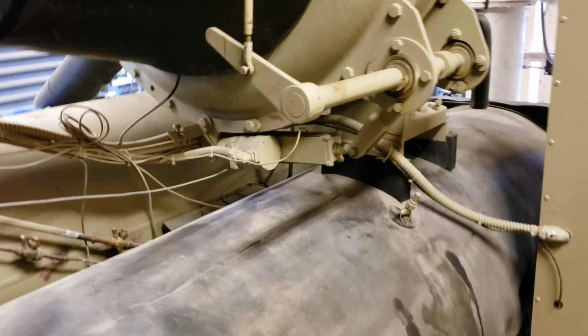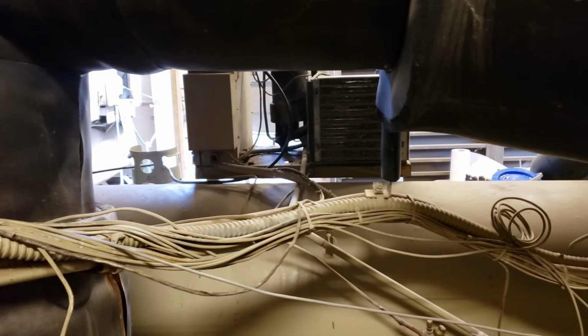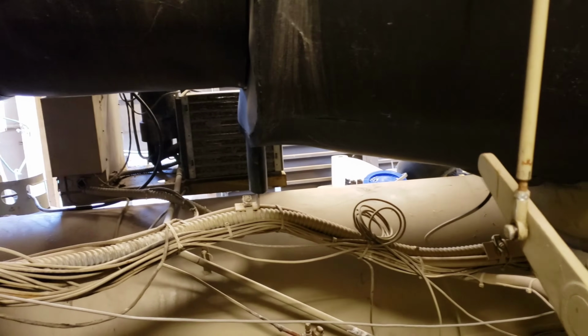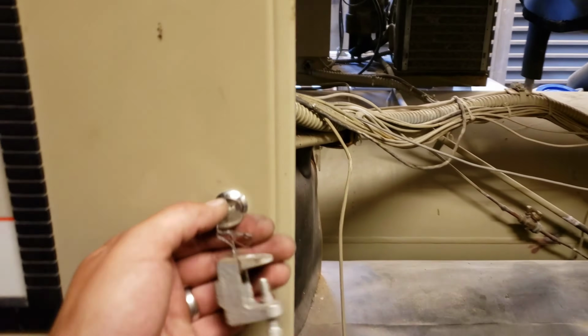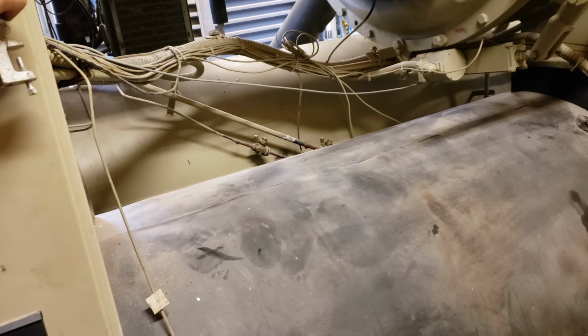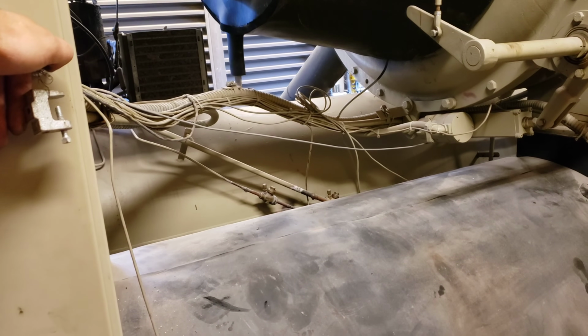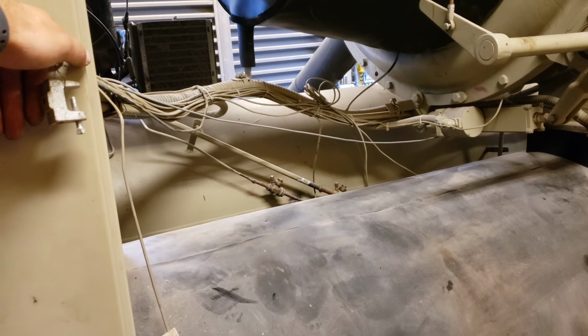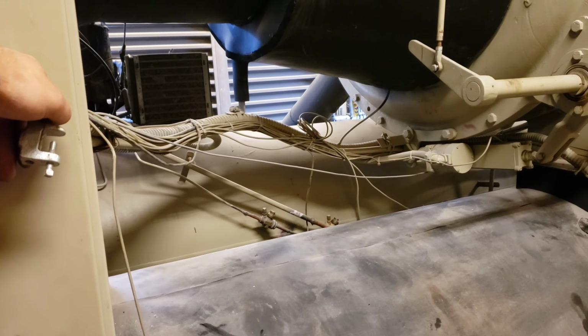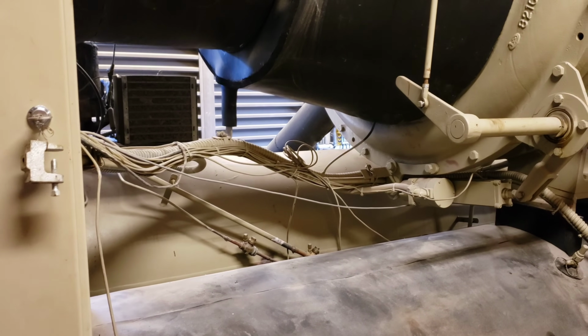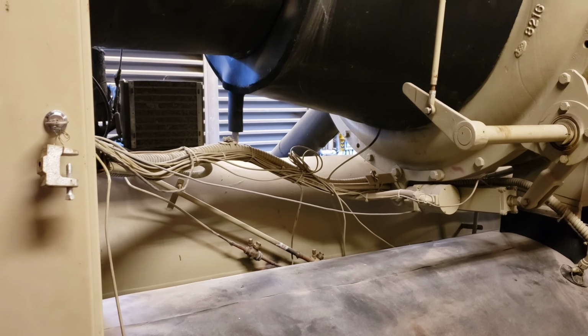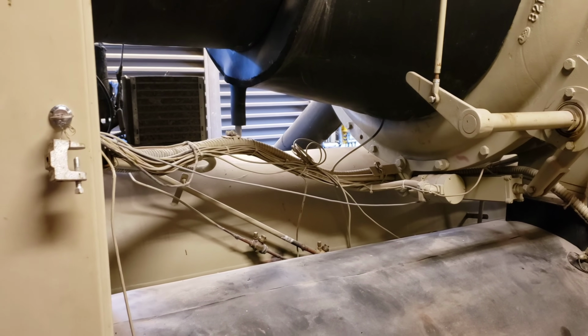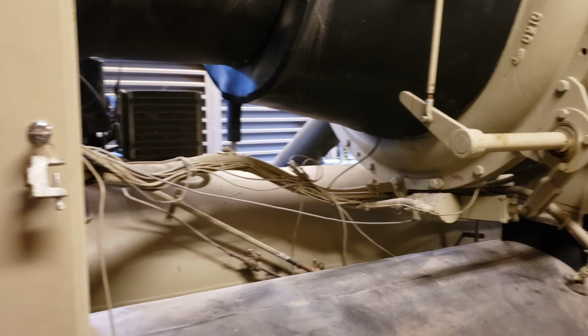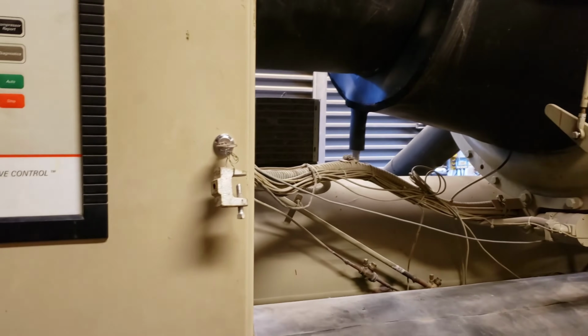If anybody's wondering, yes, all the tubes have been brushed, and we've had an eddy current done, so the condenser itself is not the issue. The cooling tower is clean. My condenser water was running about 70 degrees when all this was happening, with a 54 degree entering chill water. One of the things I did to stop the surging, just to keep it online, is I lowered the current limit down to about 45%, which is just barely anything. That allowed it to run without surge, so I was able to actually get some good run hours on it today without beating the hell out of it.